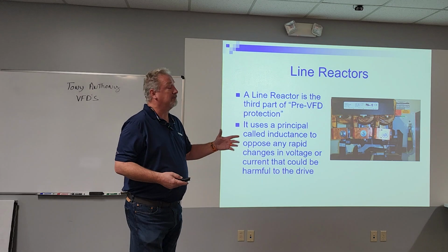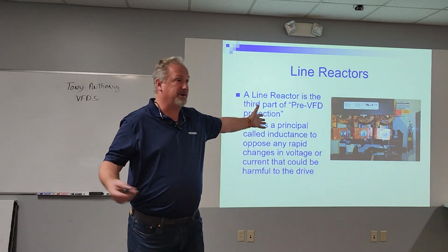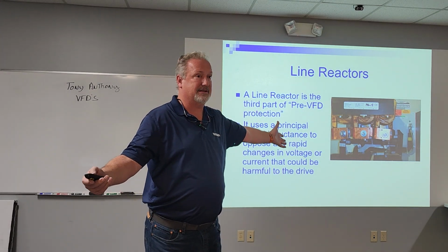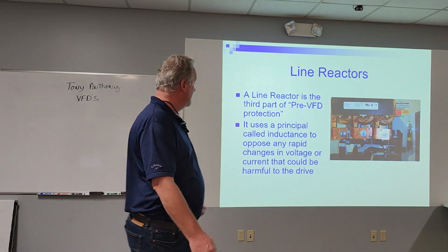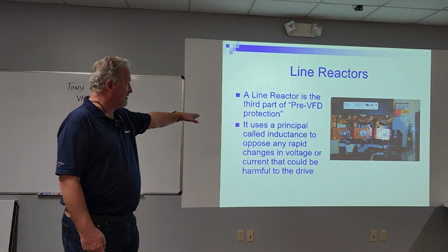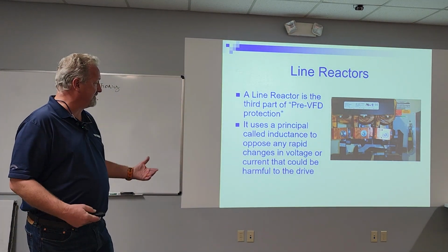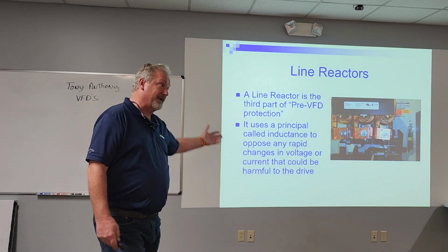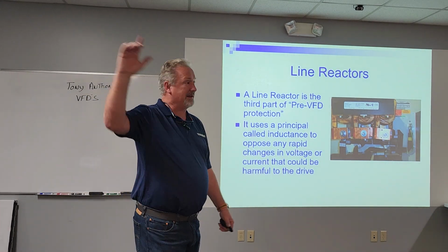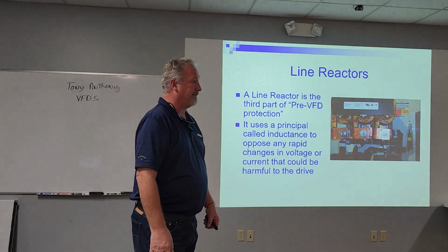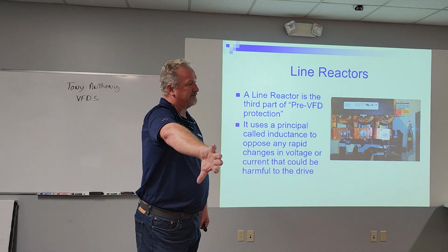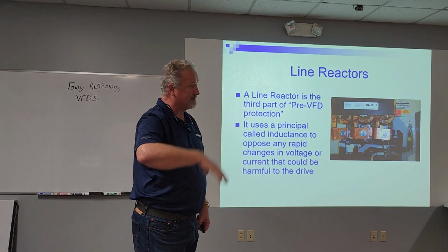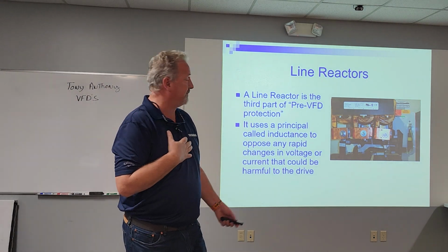Basically, this is a one-to-one transformer. It's a big coil of wire. That's all it is. By doing that, as you can see, it uses inductance. It opposes any rapid changes in voltage. That's the other thing you can do. It can protect the drive. Like if somebody hits a forklift and they get a surge through the building, that can help protect the drive from other surges or brownouts and stuff like that.